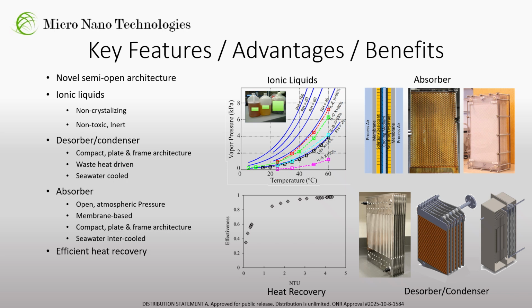The favorable crystallization characteristics of ionic liquids enable the operation of absorption cycles at temperatures, efficiencies, and configurations not obtainable with the conventional desiccants, greatly simplify the system's operational controls and support its integration with the overall shipboard HVAC system. The integrated multiplate modular desorber and condenser provide the ability to scale capacity to meet demand in a small and compact form factor. The desorber is waste heat driven, and the condenser is seawater cooled, removing these loads from the shipboard HVAC chilled water systems.